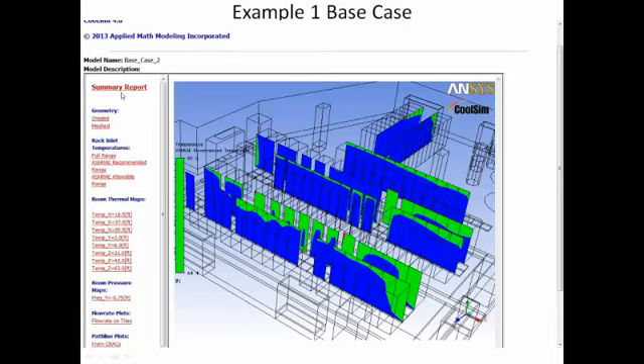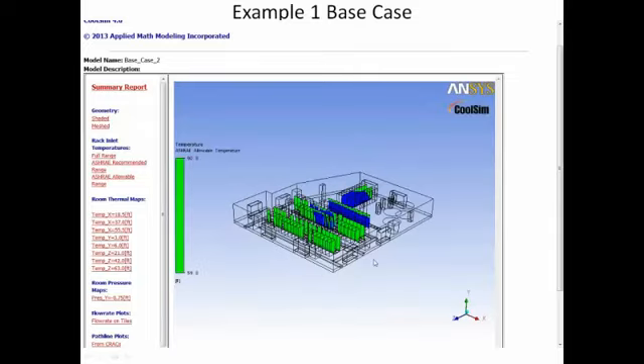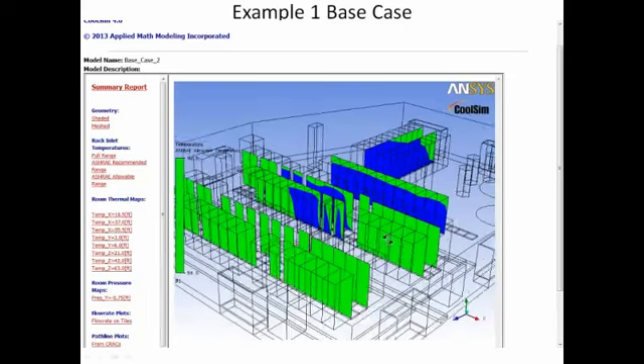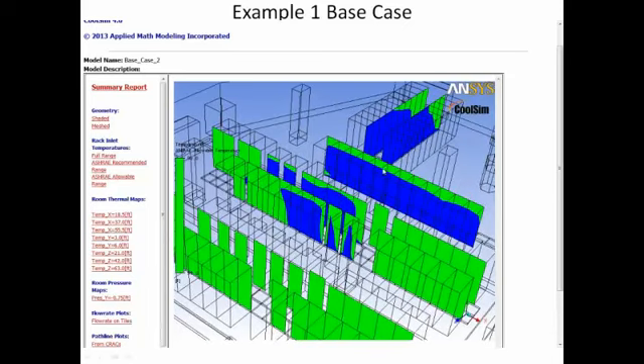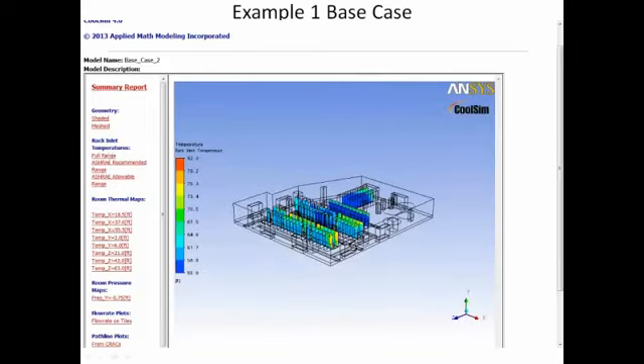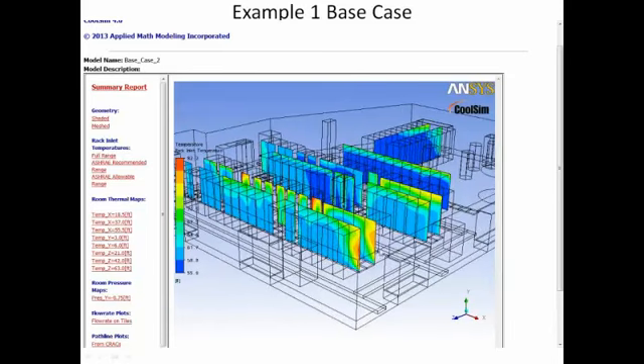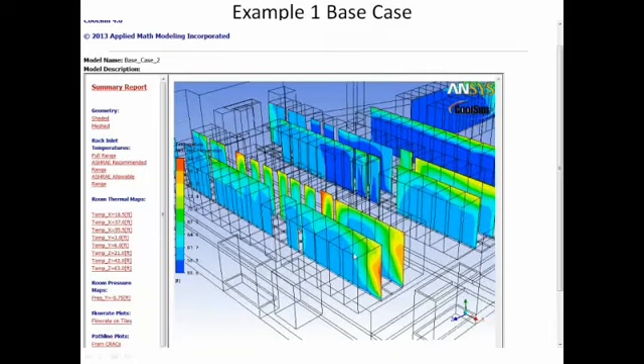Now, if I go to allowable, it gets a little better because the spec is a little broader in both directions, and I get a little more conformance, but I'm still really too cold. Now, if we look at the full range, here I've taken temperature. Again, these are automated. This comes out the same every time. But I've taken full temperature, which ranges from 55, 56 degrees on the inlet, all the way up to 82. And I've spread color out across it. So you can see the variations. You can see here that it's got some recirculation occurring in several different areas. And maybe it's good to point out that these planes, the colored planes we talked about before, are right at the intake to the electronic equipment.